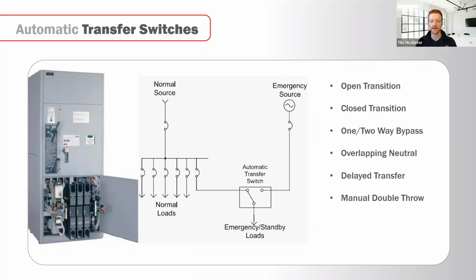Typically these standby generators are firing up in less than 10 seconds, as is required by code in most cases. Sometimes, though, there are buildings that are more mission critical and choose to back up their entire load, in which case the ATS would connect all of the loads in the building to the generator during the power failure.